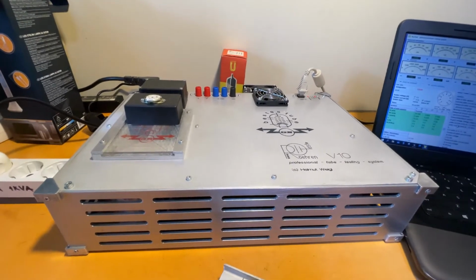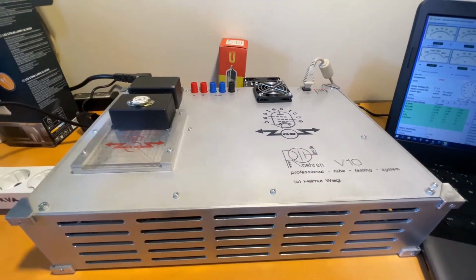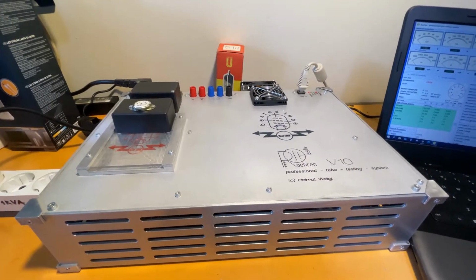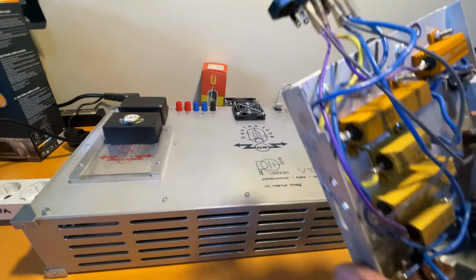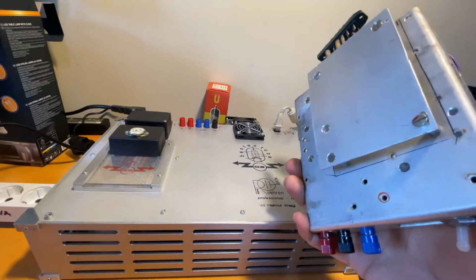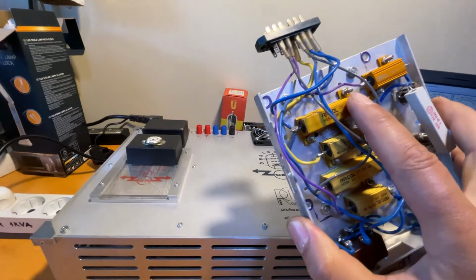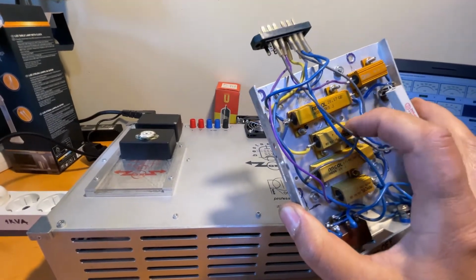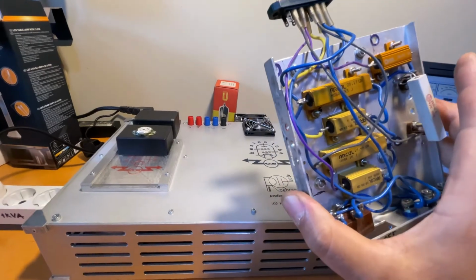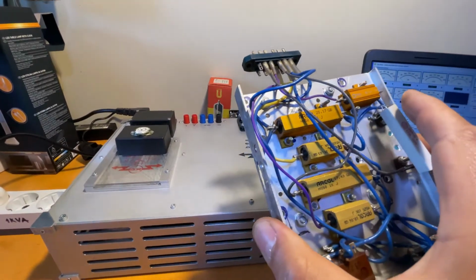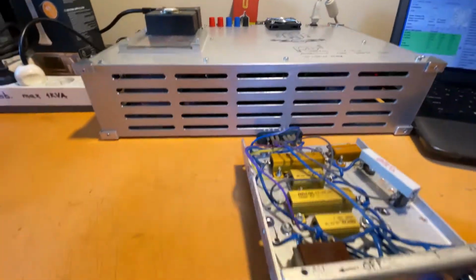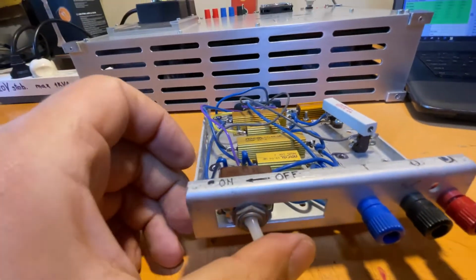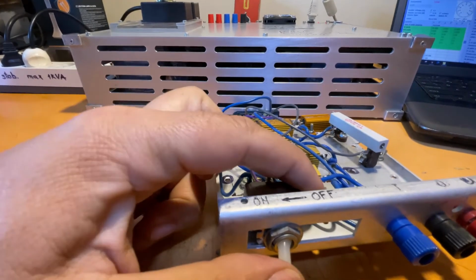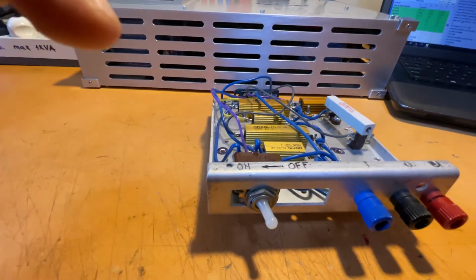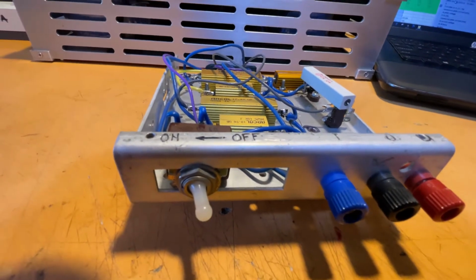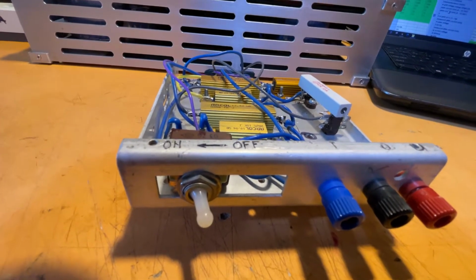This calibration is easy to do. The software helps us very much. All we need is a calibration box. This one is just some resistors, load for current calibration. Not so nice, but it's very good. This calibration box has a switch. This position is to set the drop from heater or filament voltage.